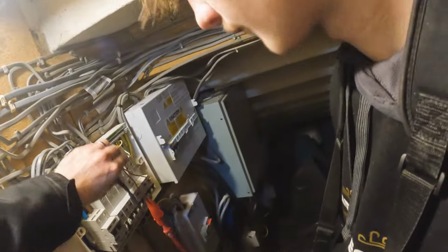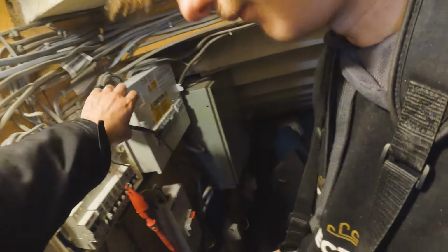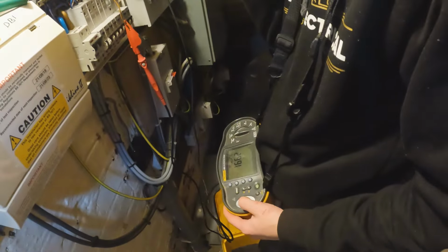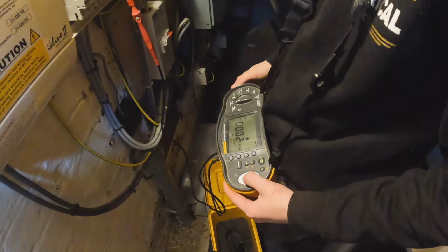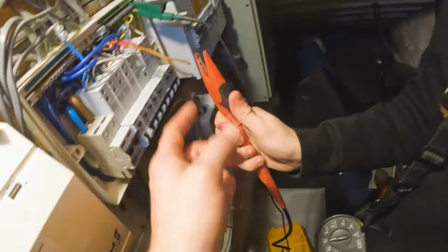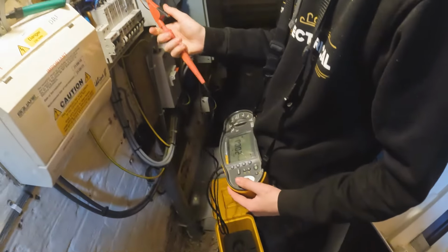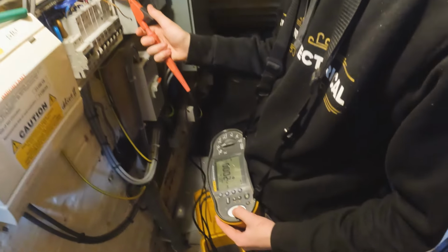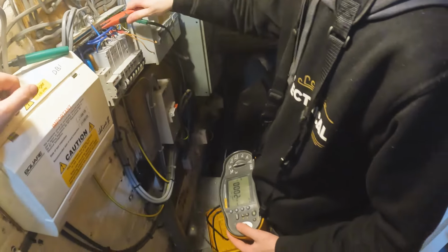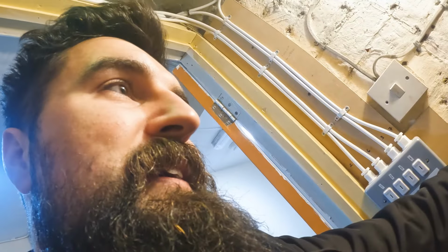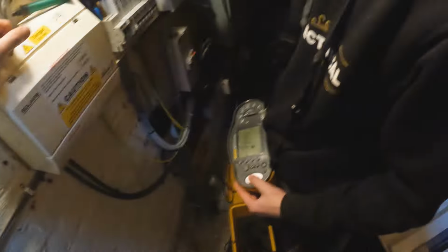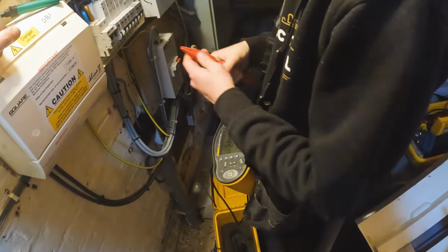And you're doing line to earth, neutral to earth, aren't you? So continuity, press test. For this one you have to hold it down. Greater than 2,000, and then we'll try the other line, nice and quick. Getting greater than 2,000 on the neutrals. You never know. To be fair, short circuit, I'm talking rubbish. Short circuit is line to neutral or line to earth only.